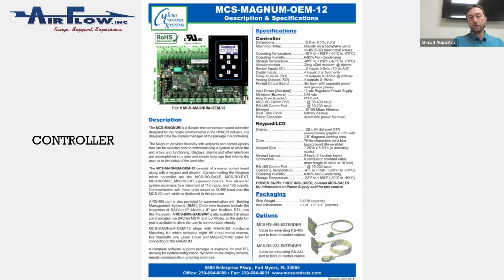Why are we talking about open protocol? Because that's a big issue for the end user when he needs access but isn't allowed to get it. In the MCS Magnum controller, you have different types of languages to communicate with your BMS. You can have Modbus, LonWorks, BACnet, MSTP, IP, or other communication languages. That's in brief what differentiates an open protocol from a proprietary one.